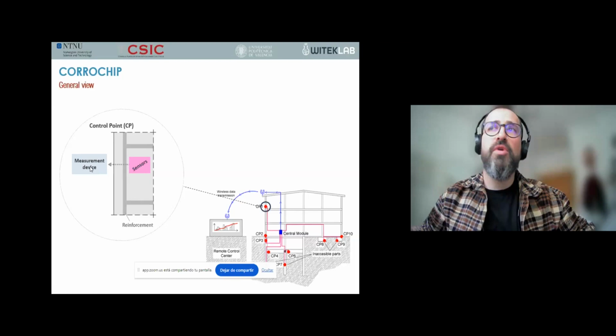Let's start from a conceptual point of view. Corrochip, as Roman Bataller indicated, is a system designed to form an integrated network of sensors. This means it makes it possible to monitor the corrosion state simultaneously at different points of a structure, even in inaccessible parts. To do this, in each evaluated zone, there is a series of sensors with measurement electrodes embedded in the structure, and electronic components placed externally to facilitate possible maintenance tasks.